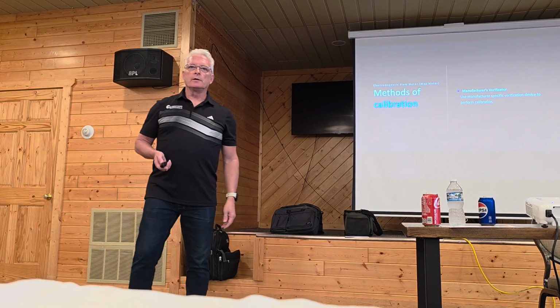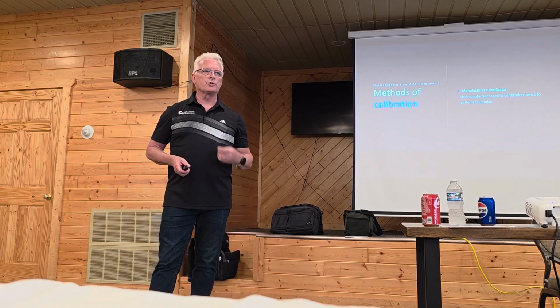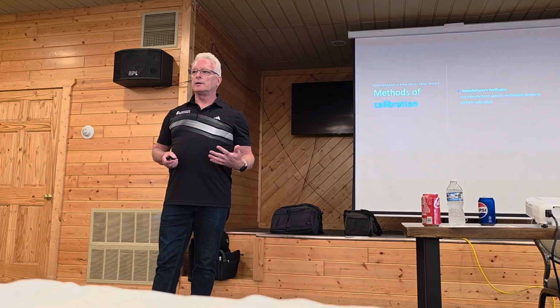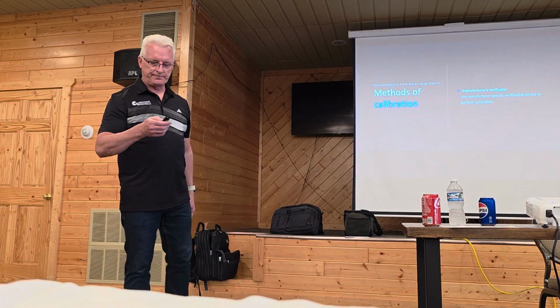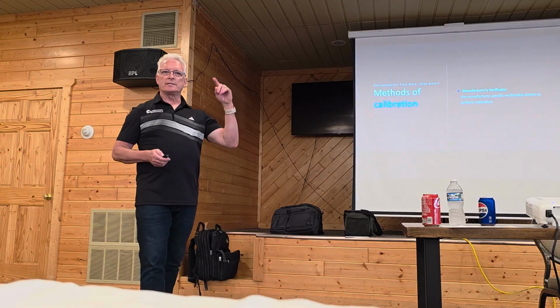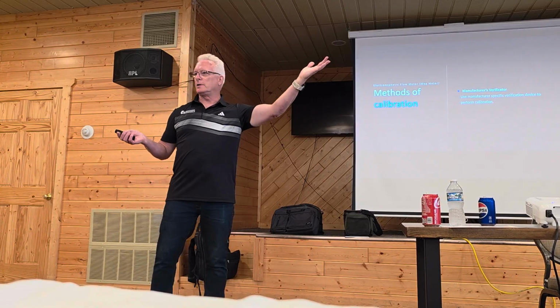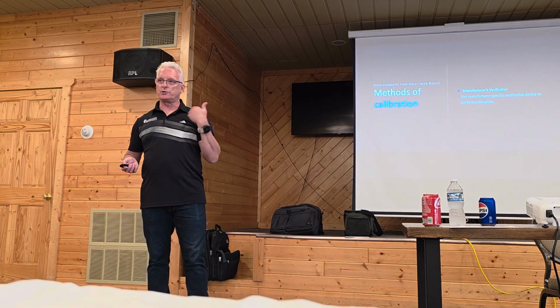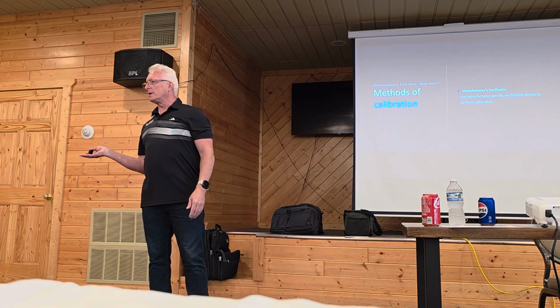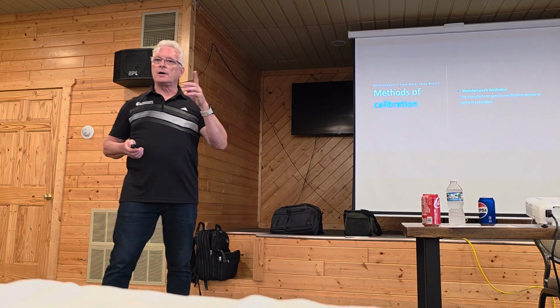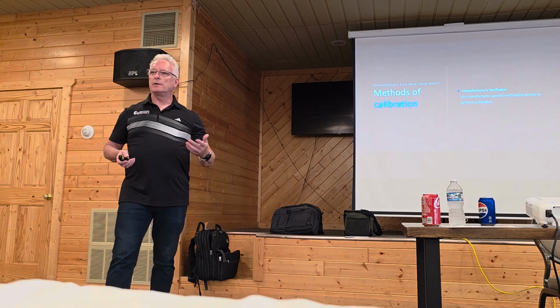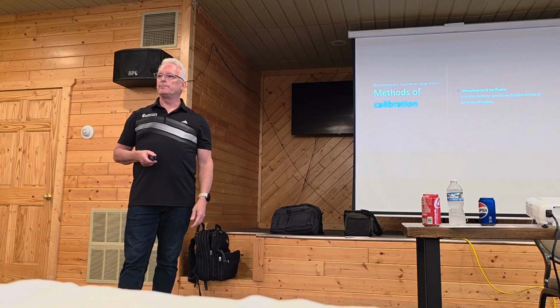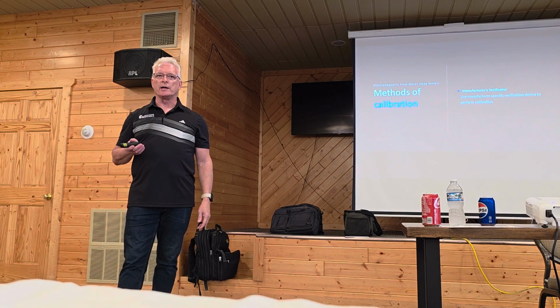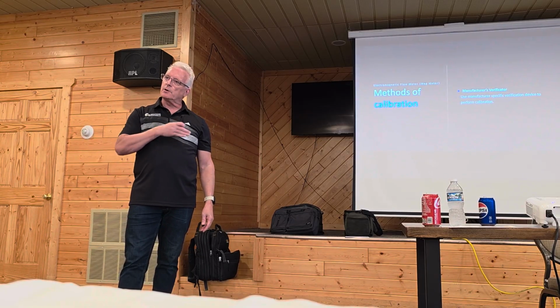So we talked about this, the manufacturer's verificator, which is usually on mag meters. They have a verificator to verify them. So the number one way, sending it in with measured water, hardly anybody does that. Second way is the verificator, which is what we prefer to do. Third way is the clamp on. And then we do have a test rig that has a mag meter that actually goes to 1/4%. So we like ours to be a little bit better than what we're testing.